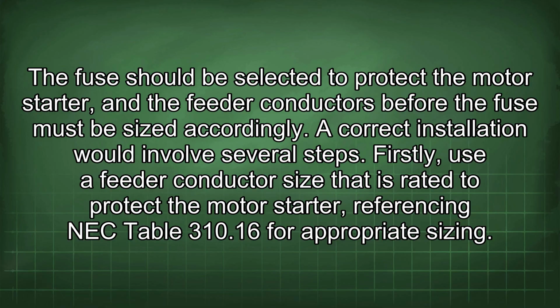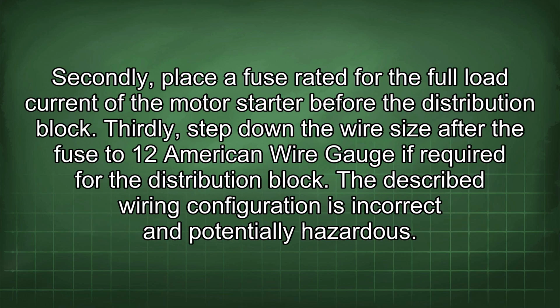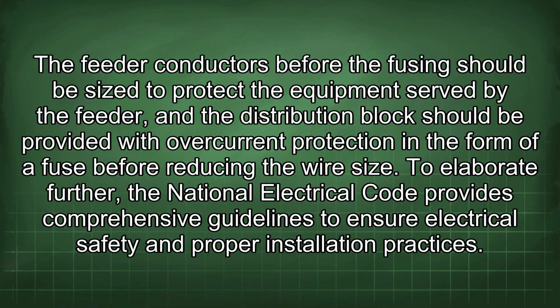Firstly, use a feeder conductor size that is rated to protect the motor starter, referencing NEC Table 310.16 for appropriate sizing. Secondly, place a fuse rated for the full load current of the motor starter before the distribution block. Thirdly, step down the wire size after the fuse to 12 American wire gauge if required for the distribution block. The described wiring configuration is incorrect and potentially hazardous. The feeder conductors before the fusing should be sized to protect the equipment served by the feeder, and the distribution block should be provided with overcurrent protection in the form of a fuse before reducing the wire size.